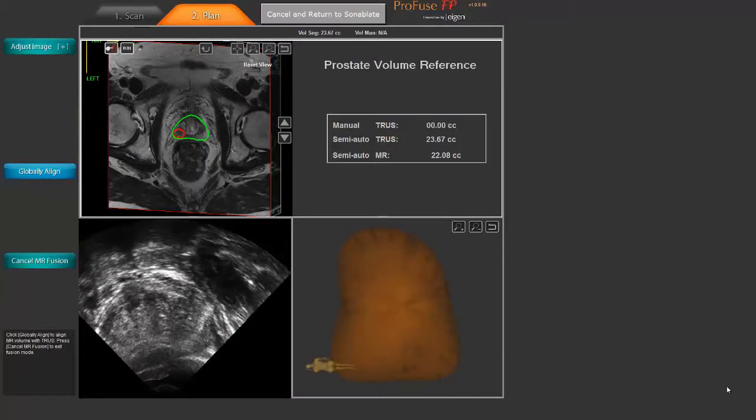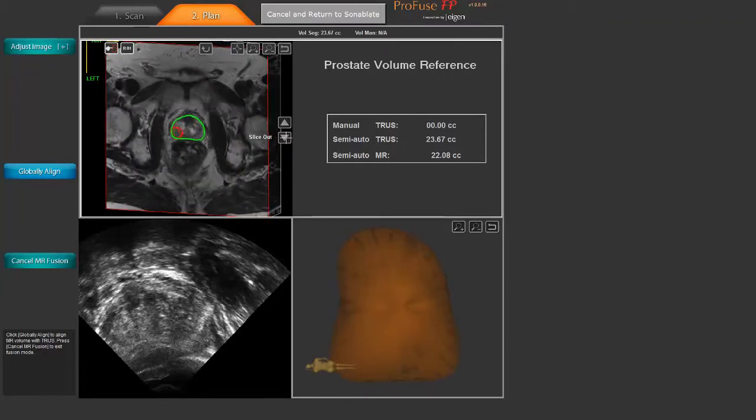We're going to be using a novel software today in which the same software package that I used for diagnosis — that's called the Profuse package, it's part of the Artemis technology — that same software package has produced a model of the prostate showing me exactly where the regions of tumor are. Now we can load that model onto the Sonablate treatment device and direct high-intensity focused ultrasound energy to exactly the regions of the prostate where the cancer is found at the time of diagnostic MRI and Artemis fusion biopsy.